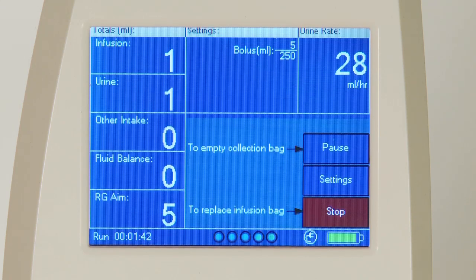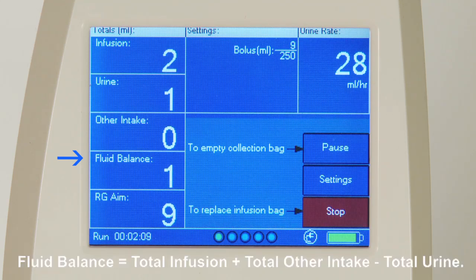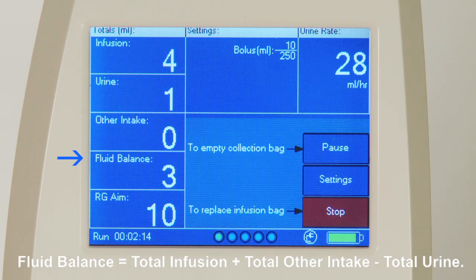Let's walk through the values displayed on the screen during operation. Total infusion: total fluid infused by the RenalGuard since the start of treatment. Total urine output: measured by the RenalGuard since the start of treatment. Total other intake: fluid infused into the patient by other sources since the start of treatment, based on user input. Fluid balance: calculated fluid balance based on this formula. Fluid balance equals total infusion plus total other intake minus total urine.